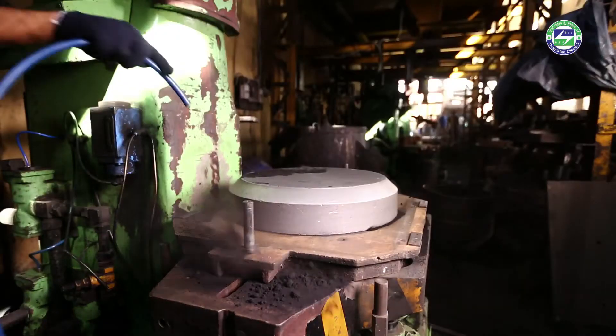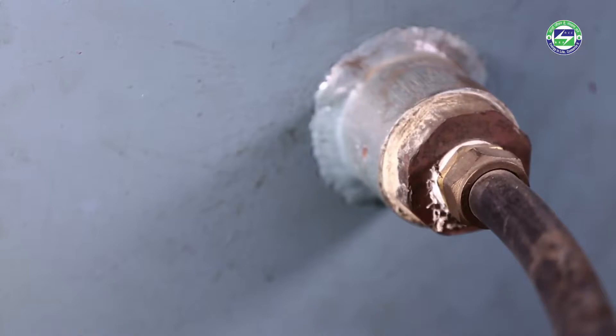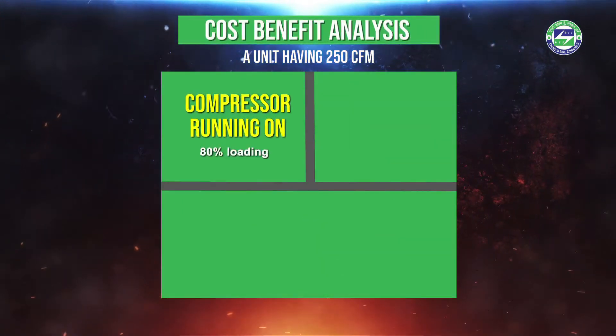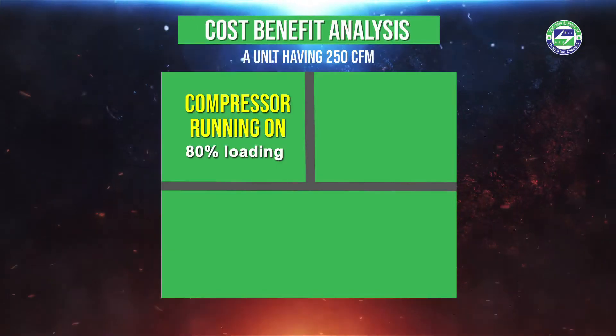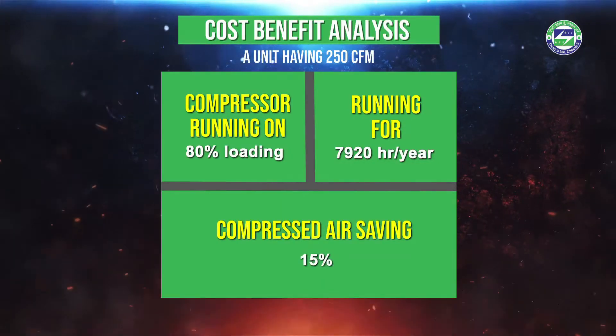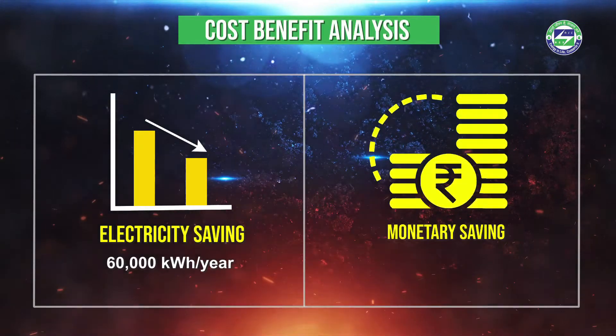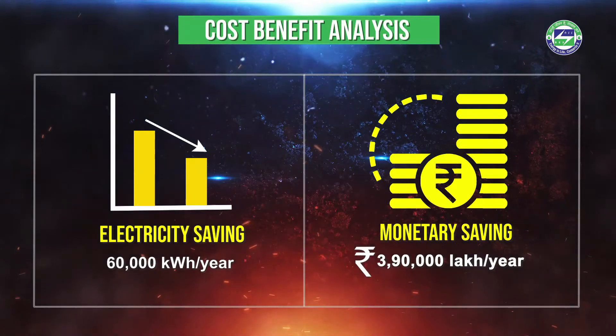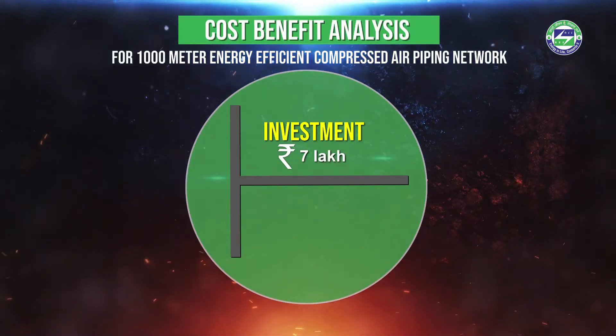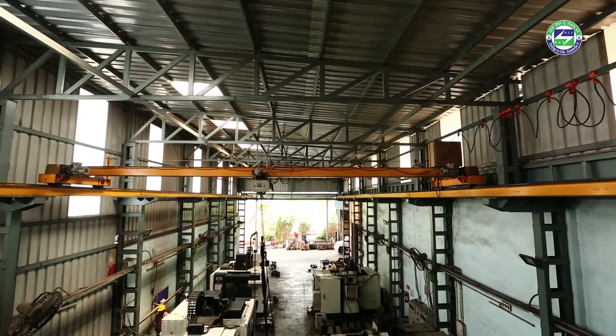To understand the cost-benefit analysis of an energy efficient compressed air piping network, consider a unit with a 250 cubic feet per minute compressor running at 80% loading for 7,920 hours annually. Considering a 15% saving in compressed air, the unit can achieve savings of around 60,000 units of electricity annually, leading to a monetary benefit of around 3,90,000 rupees. The investment required for the energy efficient piping network — considering a 1,000-meter line — is around 7,00,000 rupees, which can be recovered within 2 years.